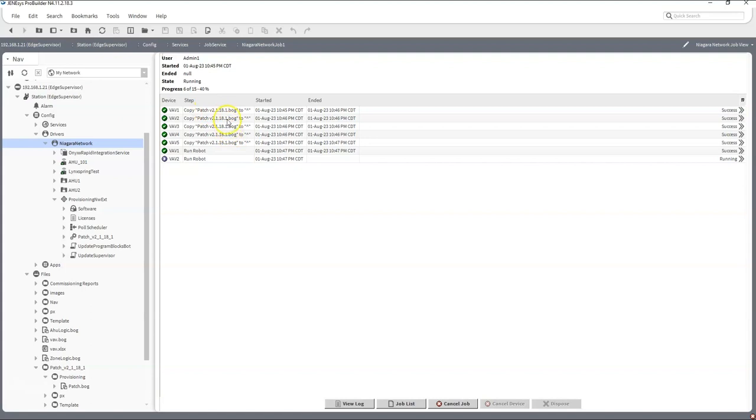So it's already copied the patch for the bog file over to the VAV and is now running a specific robot to update certain program blocks. Pretty much what this did was it was discovered in the if you set up a series fan with two-stage electric heat, or SCR heat. I think it was SCR heat, not two stage, but SCR heat. What happened was it did not switch the minimum flow properly. So while it was corrected in one of the programs when we saw it, we needed to apply a patch to make sure that we could get this out to everyone should they run into this kind of issue.